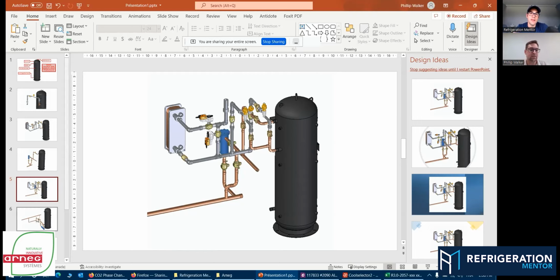Yeah, and I really like the way you did that. This is the way you should be doing it in the field. If you're new to CO2 refrigeration or even rack refrigeration, go get the piping diagram. Arneg would ship it with their equipment, I'm sure. Start from the compressors and work your way through so you know what every component is. Because if you had just shown us this, a bunch of pipes everywhere, it's hard to understand. I've been there before, where you look and there are valves everywhere, pipe going everywhere, three-way valves, and it's intimidating.